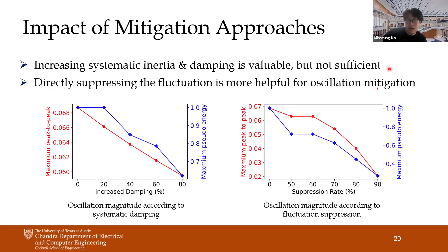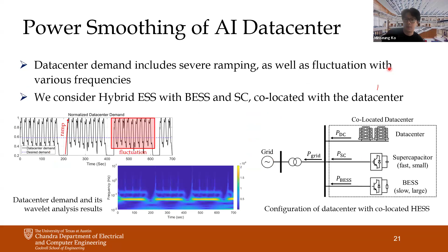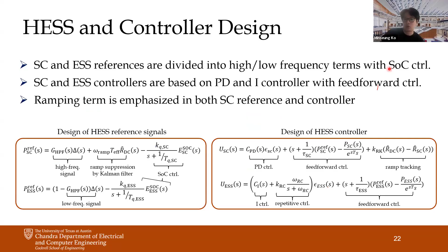Yeah, so we also tested how each mitigation approach affects oscillation severity, and our conclusion is that removing or reducing the fluctuation itself would be the best option for reducing overall oscillation severity. We have also proposed a hybrid energy storage system along with its controller and reference designs, so we could stabilize the fluctuation or frequency oscillation caused by these AI data centers.